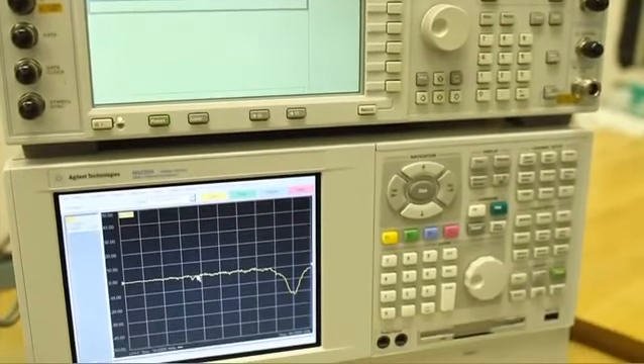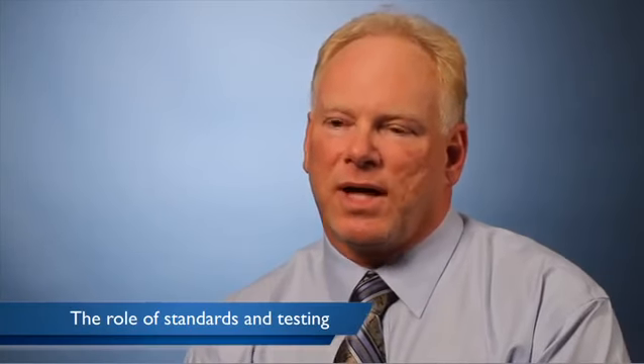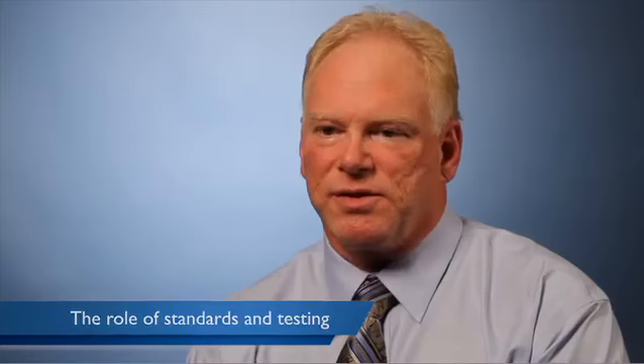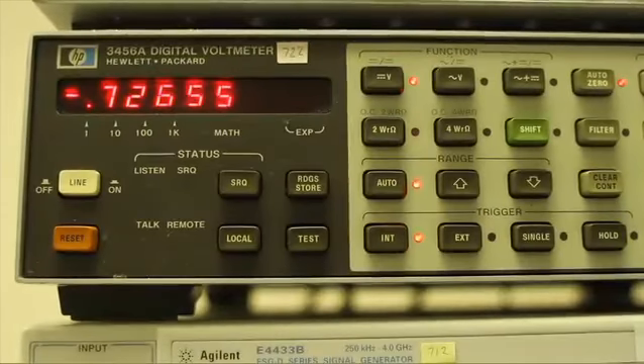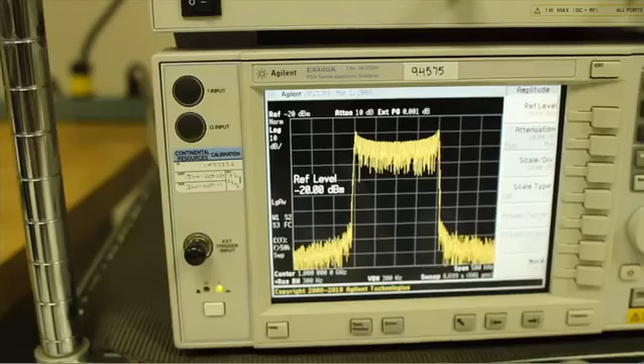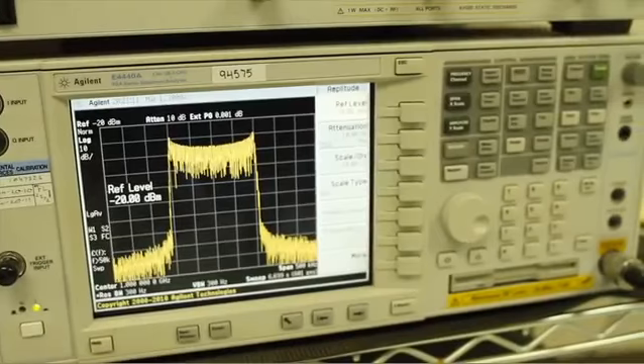In our case, we send our lab standards out to the manufacturers, have them calibrated to their original manufacturer specifications, and provide test data on the actual results, and that is used as our source of traceability.